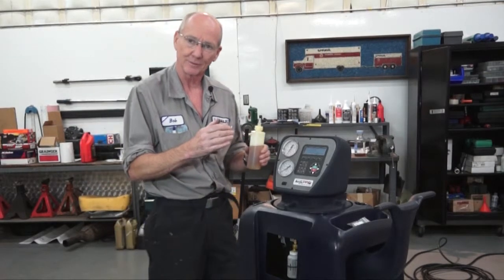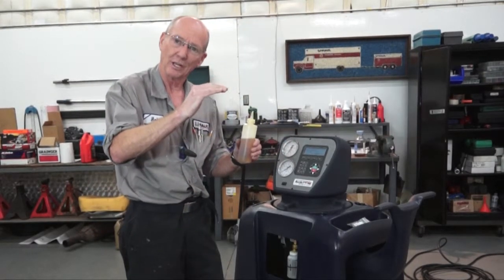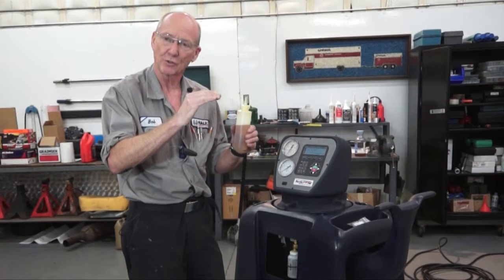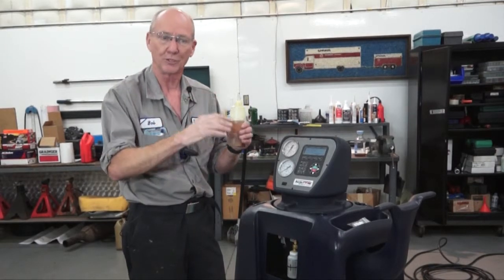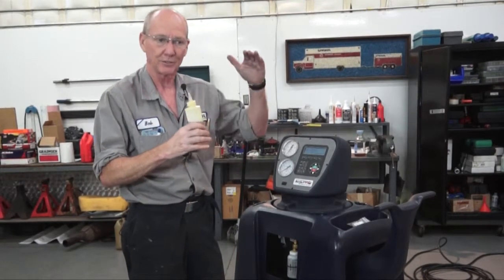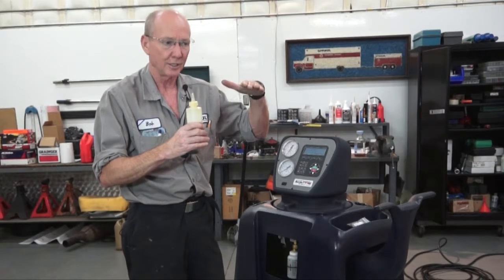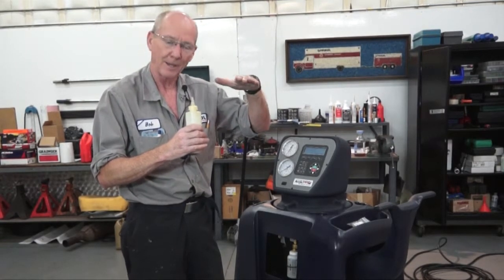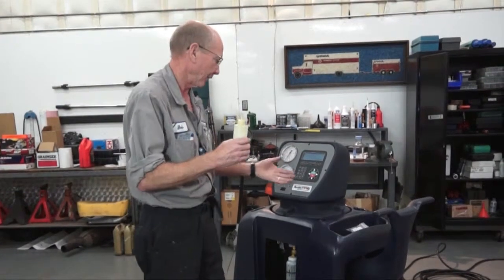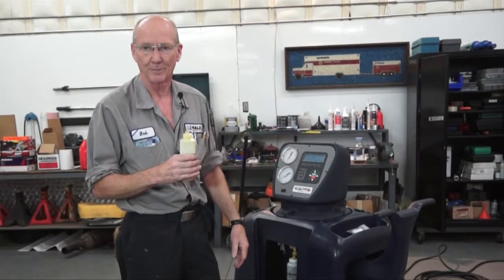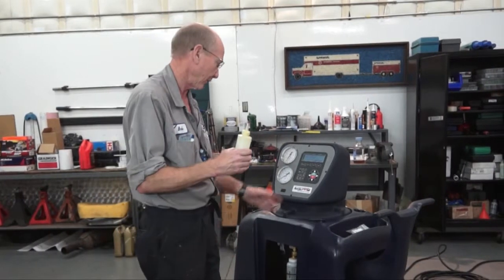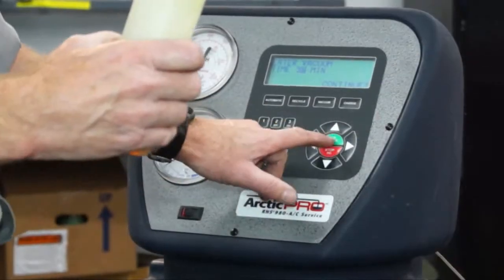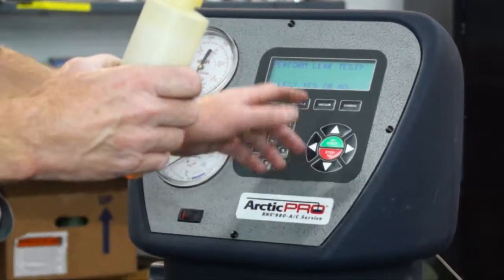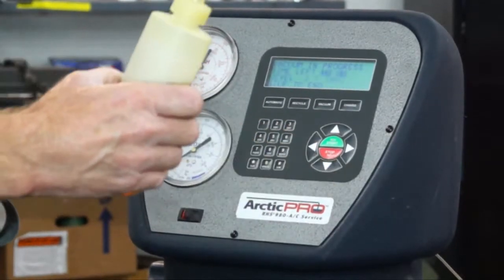As it's running, I'm going to watch the oil level through the sight glass, and I want to make sure that it doesn't go over half full. So you want to continue to fill it up because it'll use it and use it and use it until it finally evens out at halfway full. You don't want to overfill it. If you overfill it, it'll decrease the performance of the vacuum pump. They're a little touchy. So I'm going to hit enter vacuum time, yes, continue. Perform a leak test, I'm just going to hit no.